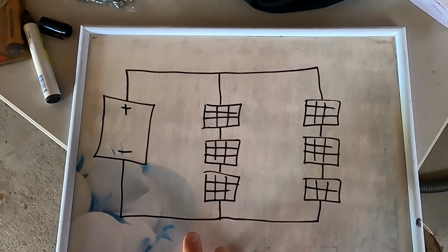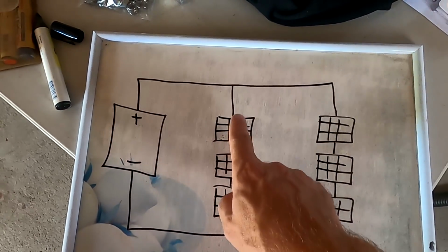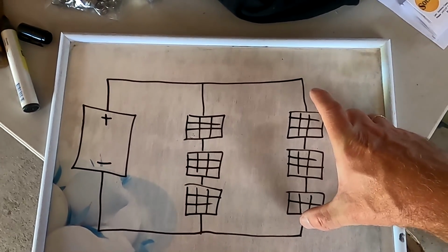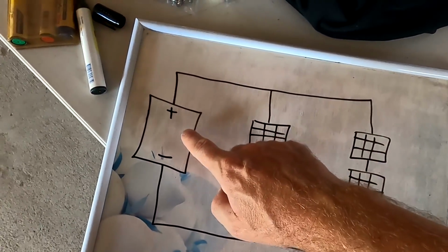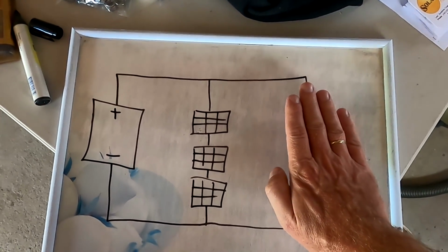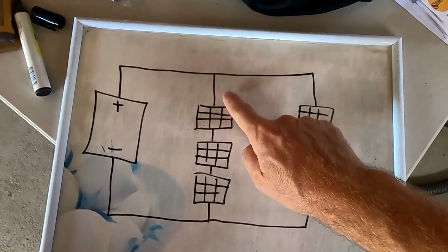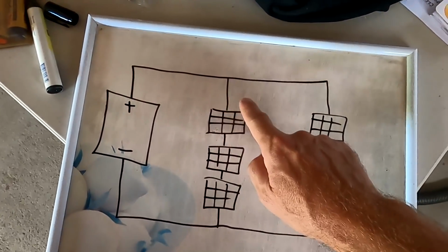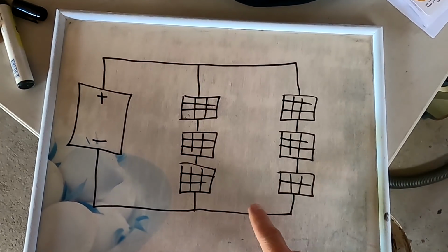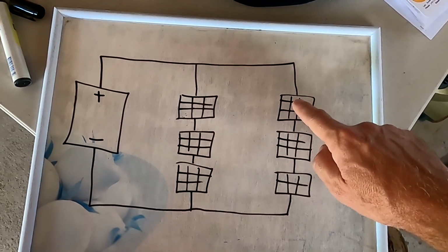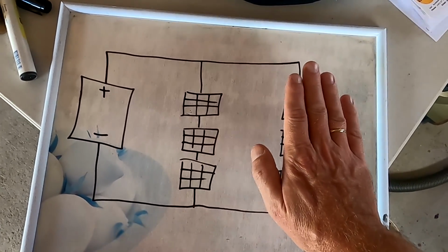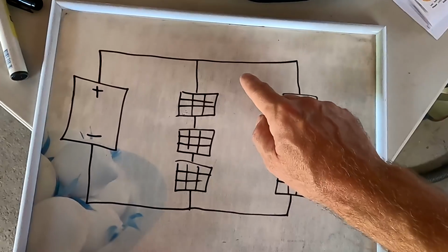And this is the situation we have at the moment. I've got three panels in series. I've got another three panels in series. And these strings are put in parallel into our solar charge controller. So if I would shade one of these panels, people think that energy is flowing into the charge controller as well as into this part of the solar system and backfeeding these panels here because they have a lower voltage. They are shaded. They don't produce any power.